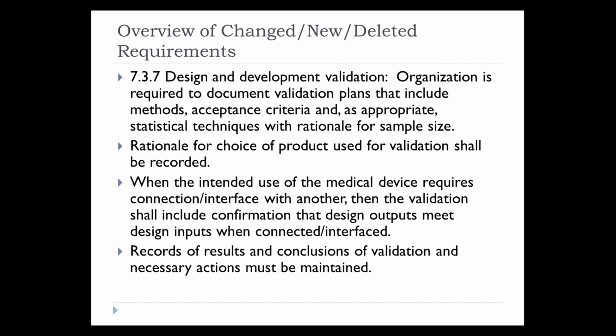Again, very similar to verification, when the intended use of the medical device requires connection or interface with another device or unit or hardware or software, the validation shall include confirmation that outputs are meeting input requirements when that connection or interface is functional. And the records of the validation efforts and any resulting actions have to be maintained.